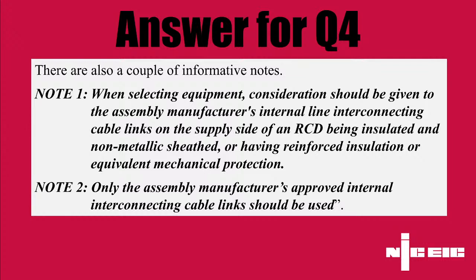So yes, our advice would be always that, because effectively where you've got two sources of supply, you're going to have two characteristics, and if your downstream final circuits or distribution boards have got protective devices, they need to be confirmed that they will operate effectively regardless of which of the two supplies and the characteristics that you're going to be supplying them with. So yeah, if it's back at the origin, then we talk about recording two sets of values for all of those characteristics of the two different supplies. Now this is one of those situations where your standard template of your certificates only caters for one, so you're going to have to come up with a second way, a continuation sheet, some other form to add to it. But yeah, definitely advisable to do it, because it does so many things.